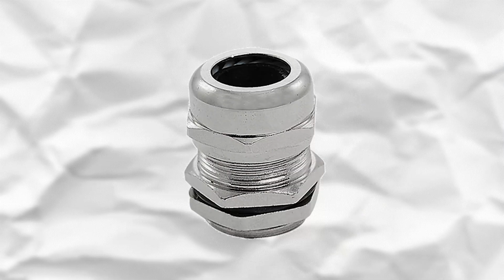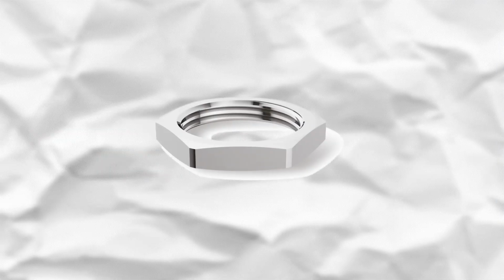JB construction material should be die-cast aluminum or stainless steel, and the amount of copper is not allowed to exceed 0.4%. IP degree should be 65 at least, and an explosion-proof certificate for JB is required from the manufacturer if it is installed in a hazardous area. To fix a cable on the junction box, a cable gland is used. It can be tightened on a junction box by its thread connection or a lock nut.